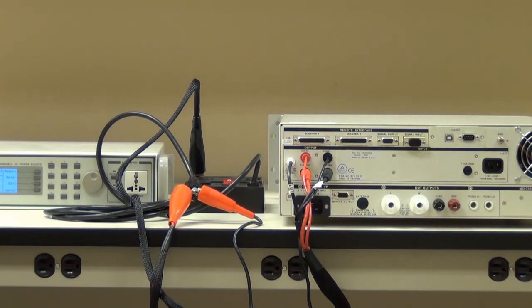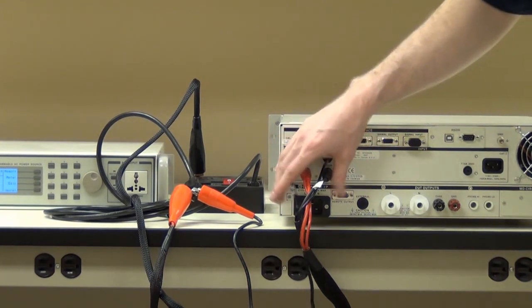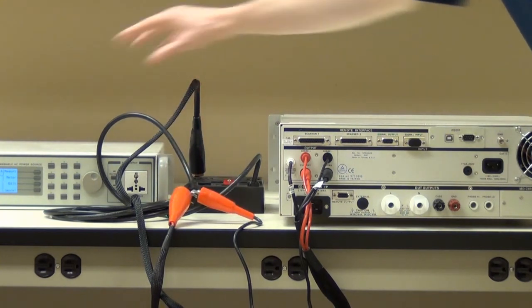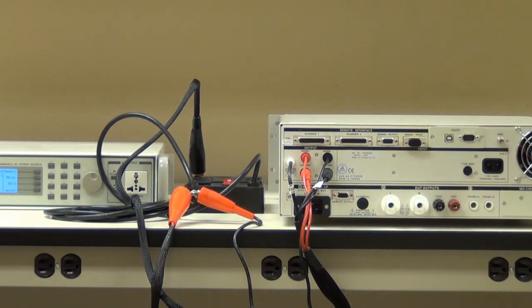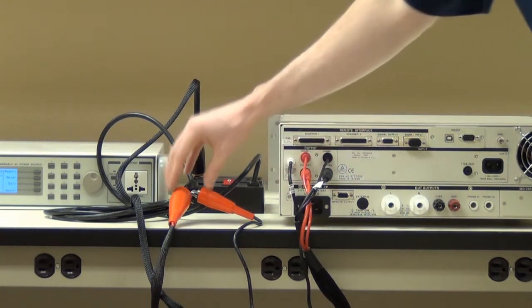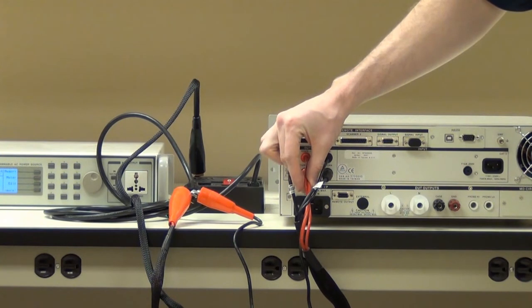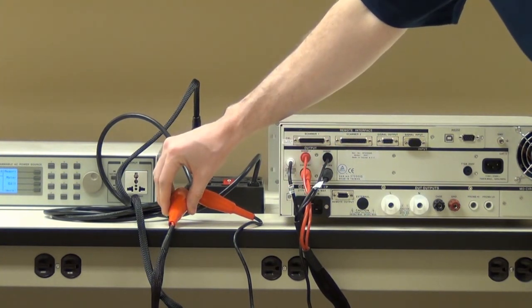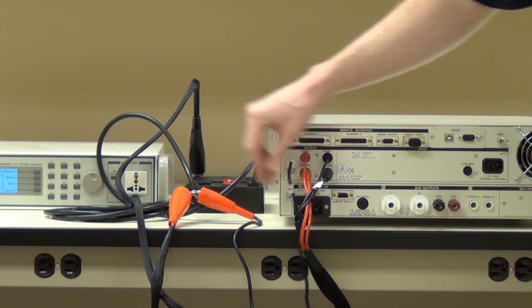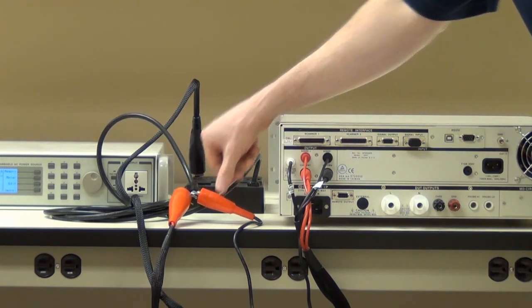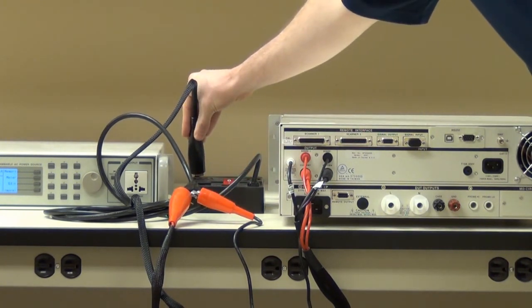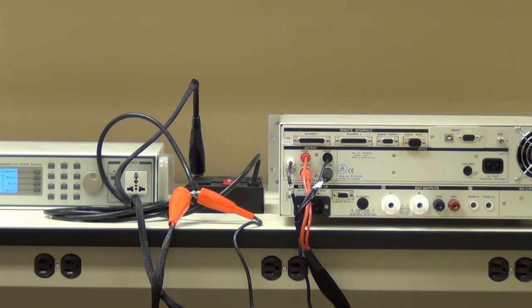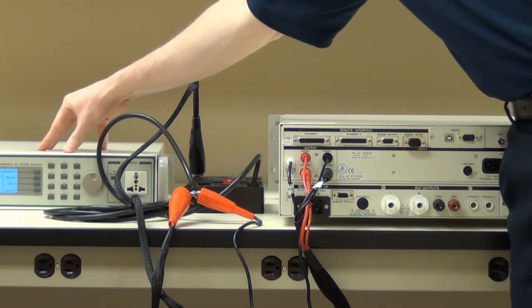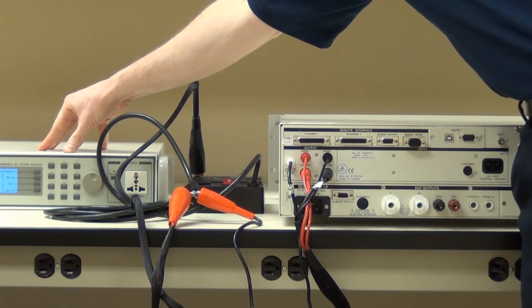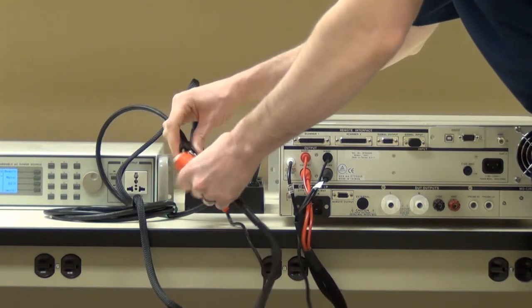The third recommendation is to always remove the test leads from the DUT prior to running any other tests. Let's run through a quick example. As you can see here, I have the Omnia connected up to a product. I have the high current lead connected to the ground pin for a ground bond test, the high voltage lead connected to the mains input for the hipot test, and then of course I have my return on the chassis. Say this sequence was done, and the operator then needed to connect it to an AC power supply for a run test.